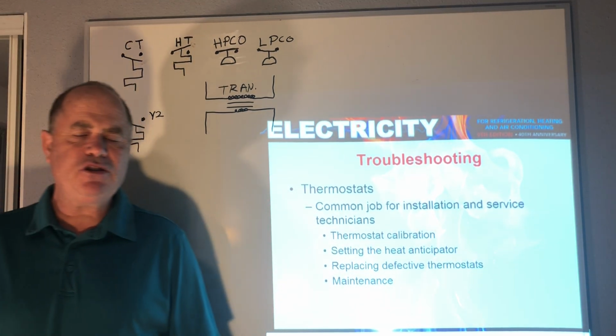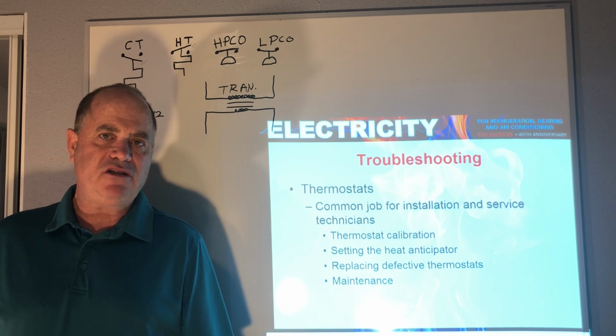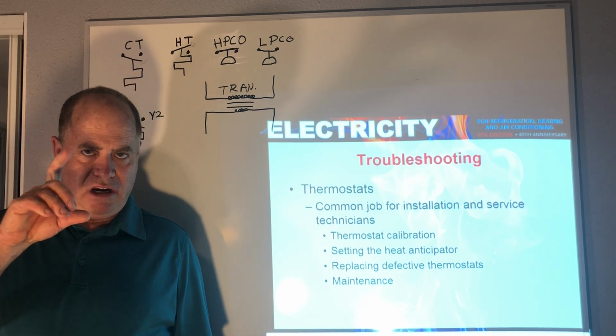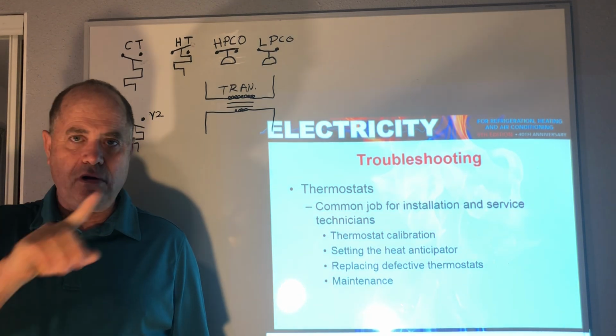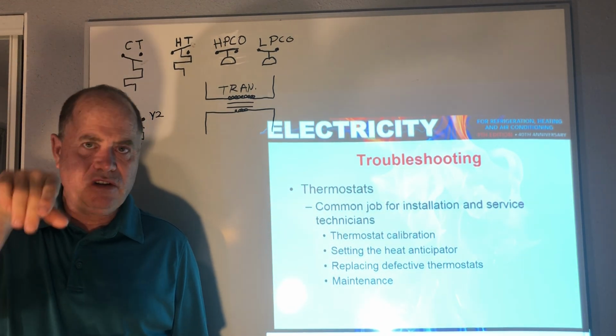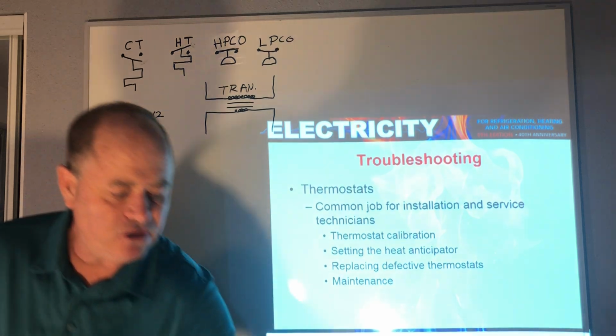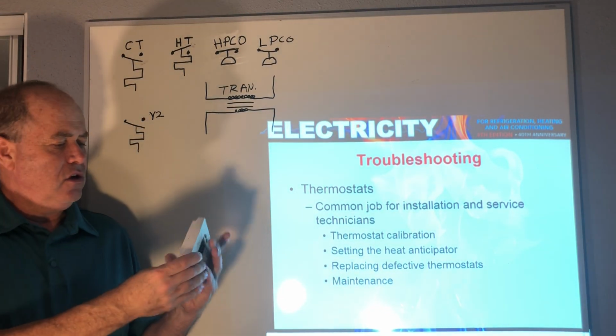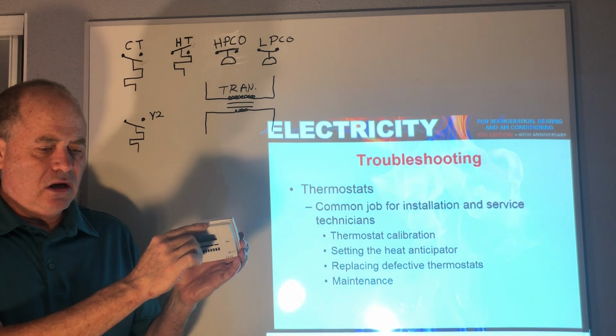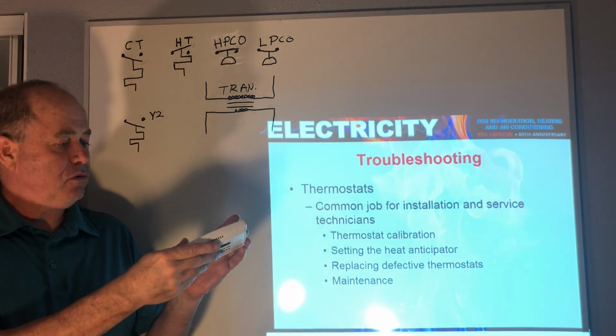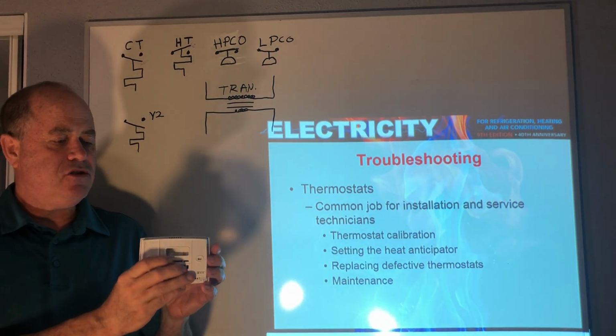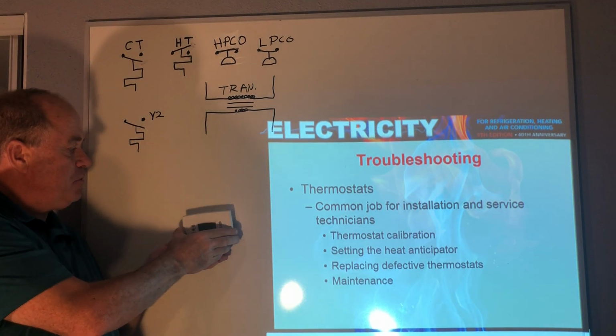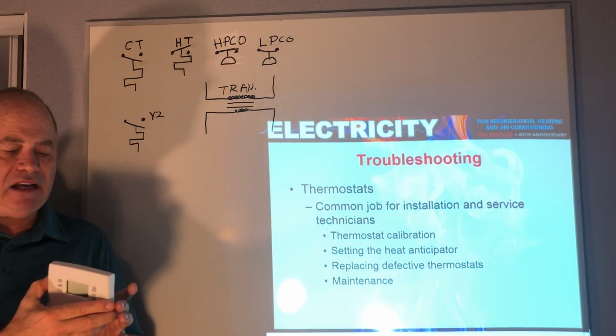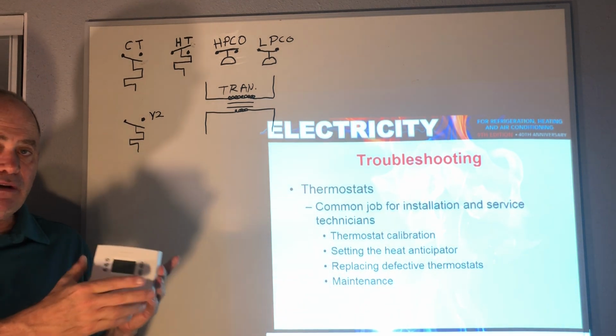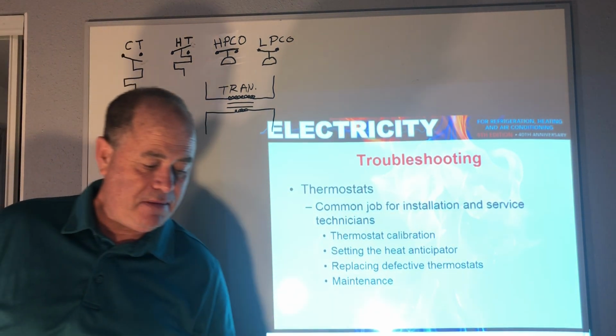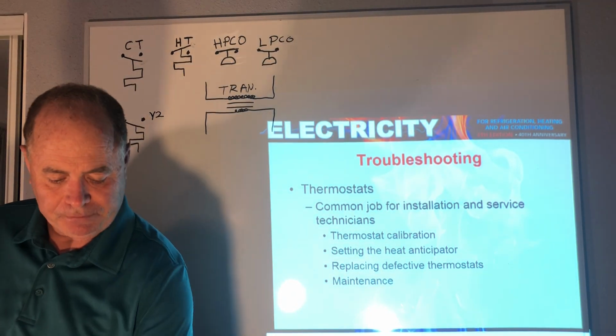On maintenance, things are pretty digital now. Keeping the thermostat clean, maybe even, you know how you use air to clean a circuit board on a computer? Getting it in there once in a while and blowing out your thermostat. You'll see most thermostats are designed with little holes that allow air to pass through them, because when you mount it on a wall, you want it to take the temperature in the room and let some of the air pass through it. So taking the cover off your thermostat and blowing it out might not be a bad idea every once in a while.